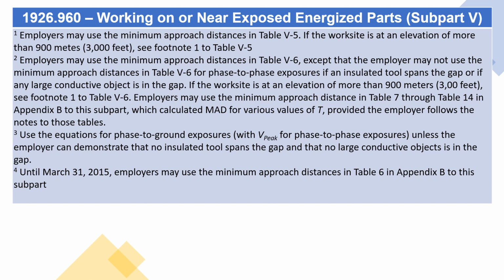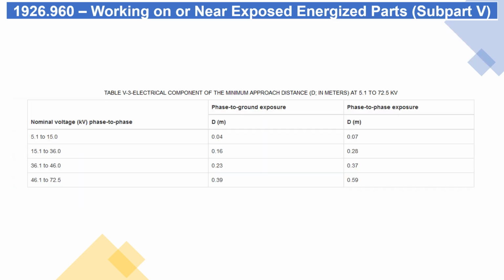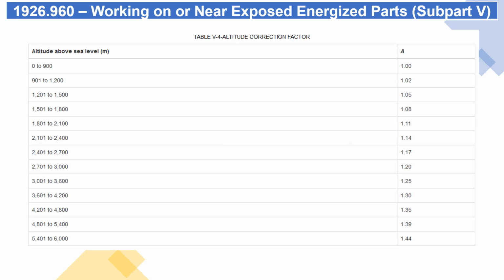Use the equations for phase-to-ground exposures, with VPeak for phase-to-phase exposures, unless the employer can demonstrate that no insulated tool spans the gap and that no large conductive object is in the gap. Until March 31, 2015, employers may use the minimum approach distances in Table 6 in Appendix B to this subpart. Table V3, electrical component of the minimum approach distance, D, in meters, at 5.1 to 72.5 kV. Table V4, altitude correction factor.